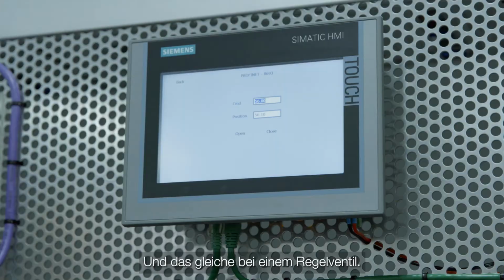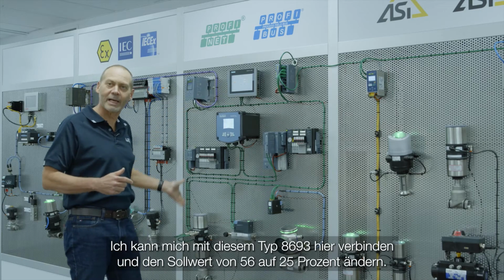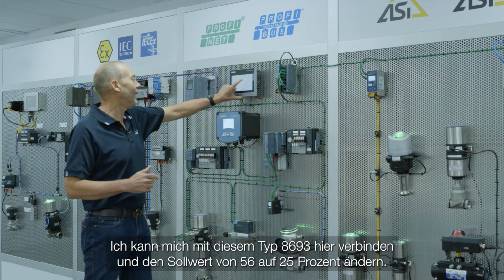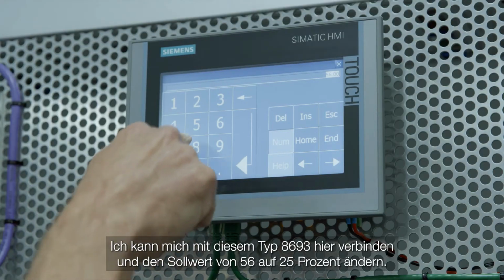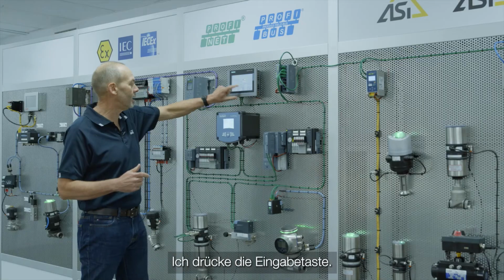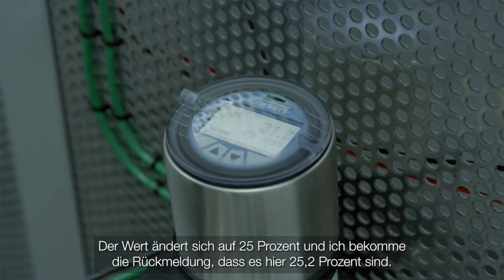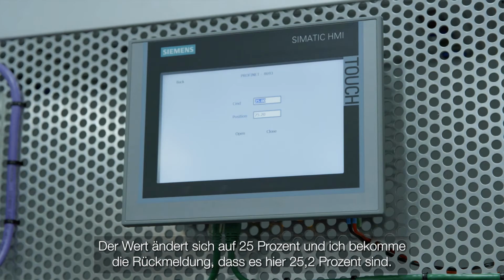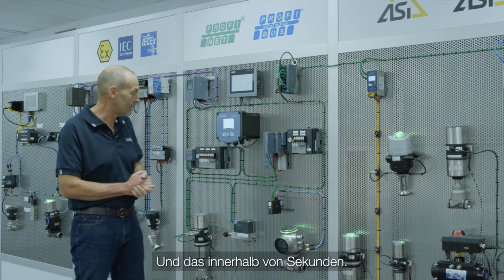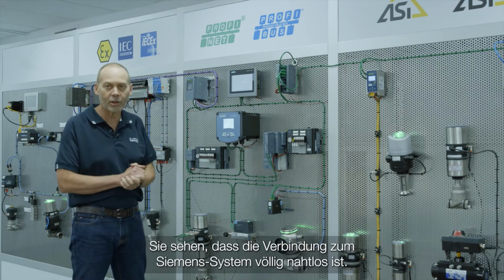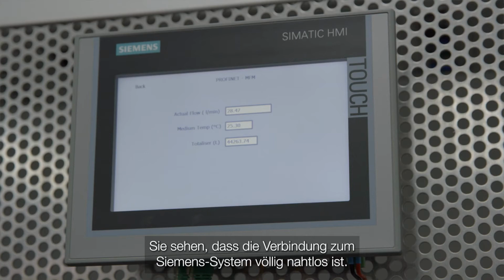And the same on a modulating valve. I can connect to this 8693 here, and let's change the set point from 56 to 25%. I hit enter, it changes to 25%, and I get my feedback telling me here it's at 25.2%, so within seconds. So the connectivity is totally seamless to the Siemens system.